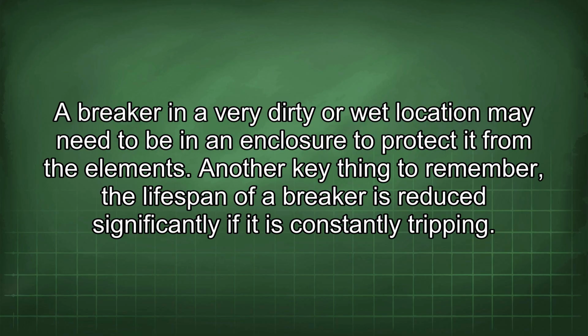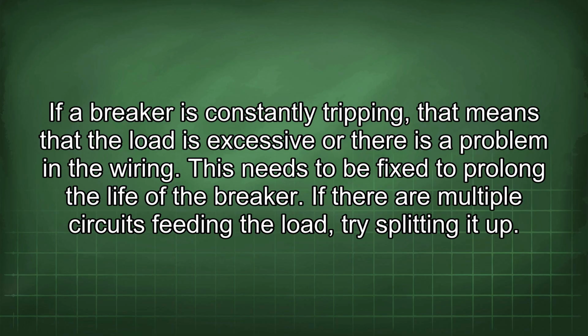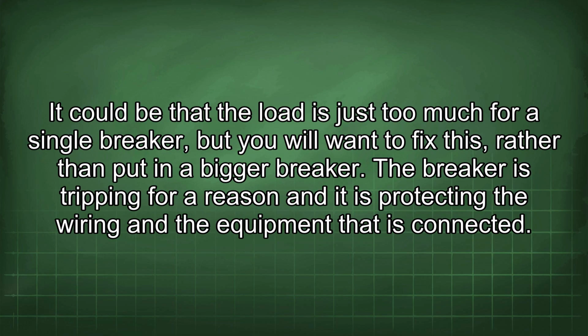Another key thing to remember: the lifespan of a breaker is reduced significantly if it is constantly tripping. If a breaker is constantly tripping, that means that the load is excessive or there is a problem in the wiring. This needs to be fixed to prolong the life of the breaker. If there are multiple circuits feeding the load, try splitting it up. It could be that the load is just too much for a single breaker, but you will want to fix this rather than put in a bigger breaker. The breaker is tripping for a reason, and it is protecting the wiring and the equipment that is connected.